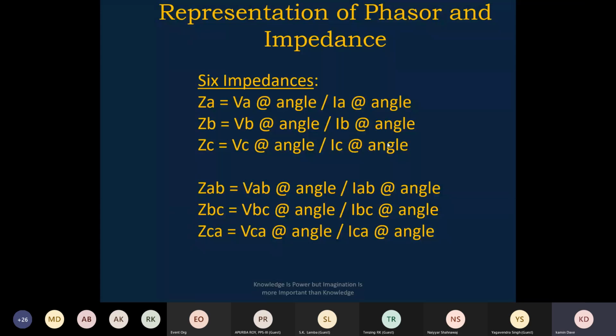Actually, according to their settings, it should not operate, but it was operated. Whereas in the other place there was a 500 megawatt machine, and there was a GT terminal fault, and the backup impedance did not operate. So the relay setting is there. The manufacturer has given a set of settings, but whether those settings are right or wrong, who can validate?